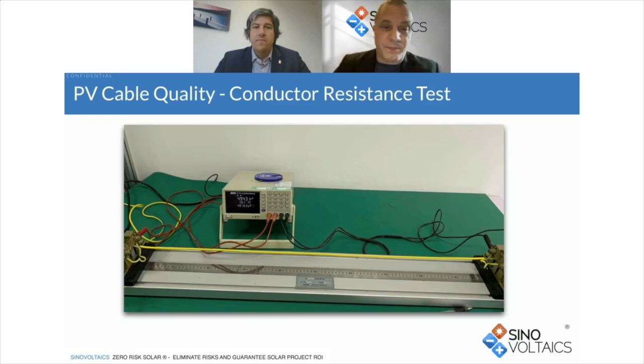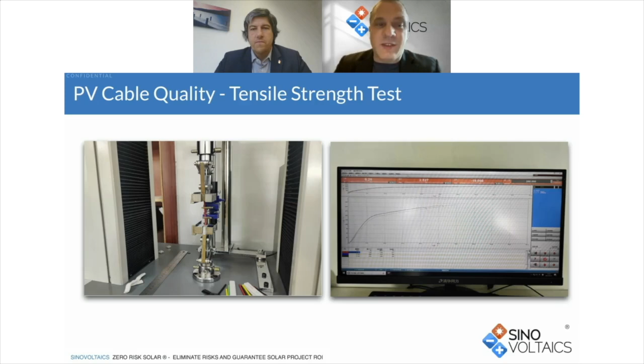Another important test where our team also sometimes comes across failures is the tensile strength test, which is conducted on the insulation and jacket respectively. And this test is to ascertain compliance with the corresponding maximum stress thresholds. Basically, with this test, we measure the maximum stress a cable or cable materials can withstand before they fail, for example, stress they're exposed to during installation or in their operational life. Tensile strength is indicated normally in Newton per square millimeter or megapascals, and breaking elongation, and they vary for different materials.